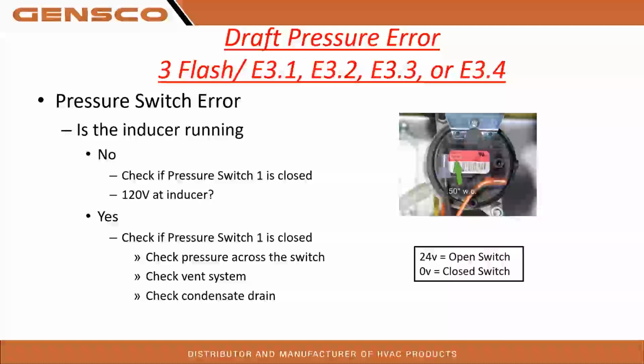So if no, we're going to see if the actual switch is closed. Maybe there's some water in the line somehow, some condensed water in that pressure switch line. Maybe it's a plugged port or something like that. So we need to figure out what's going on there with that pressure switch. If yes, we need to check the pressure switch to see if it's closed, right? So we're going to check pressure across the switch. We're going to check the vent system and even maybe the condensate drain.